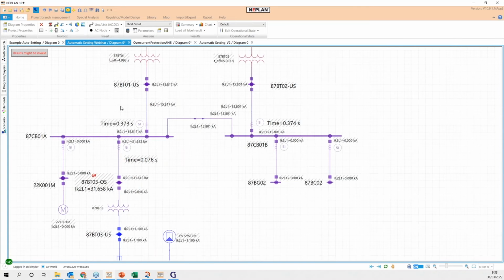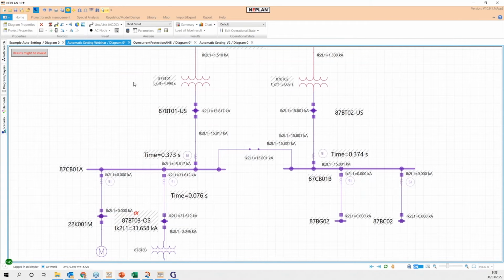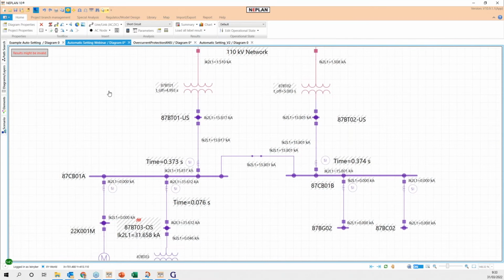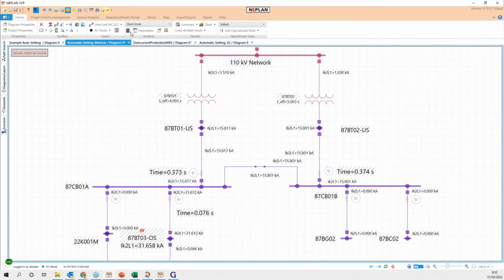So the other example that I have here is this system. This system is related to the example that I showed initially with the transformers in parallel. If I run the short circuit simulation at this point, we can see that when everything is connected, we have a selective coordination between this relay and this relay, because for this fault location, this relay is tripping first, and the difference between this relay and this relay is higher than 200 milliseconds and lower than 400 milliseconds. So everything is good in this scenario.